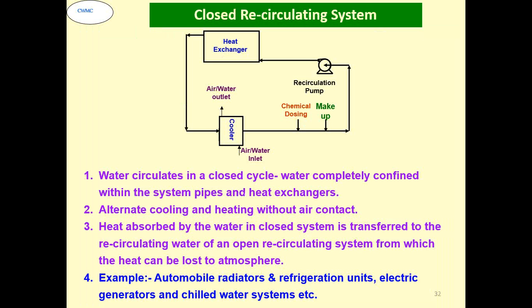The second system, which is probably the common one we are aware of, at least in our cars, is the closed recirculating system. In a car radiator, a coolant is added, and that coolant keeps on circulating inside, cooling the engine. There are hardly any losses, evaporation is less, and there is generally no makeup. So generally the problems of corrosion and biofouling are observed there, and you use corrosion inhibitors or biofouling control measures accordingly.